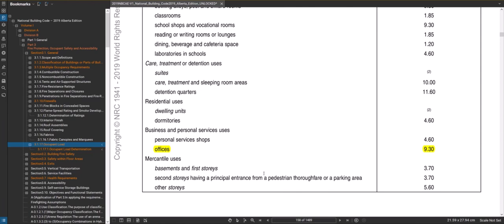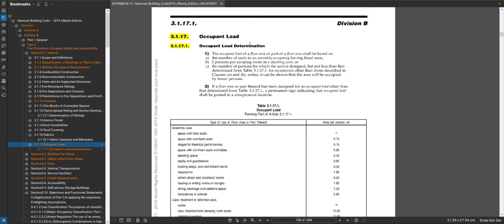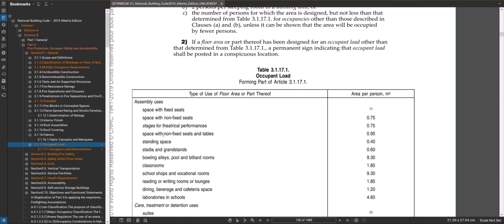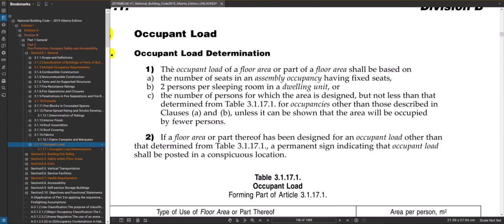For assembly uses there are many examples in the chart. If you have a space with fixed seats, the occupant load is based on the number of seats — 200 seats equals 200 people. For residential work, the occupant load is basically two persons per sleeping room in a dwelling unit. So for a two-bedroom condo unit, your occupant load would be four people.